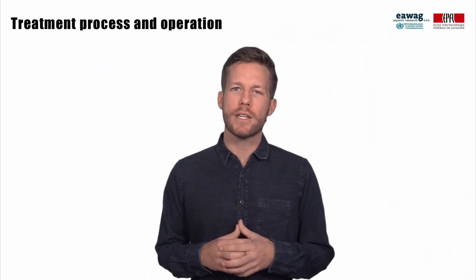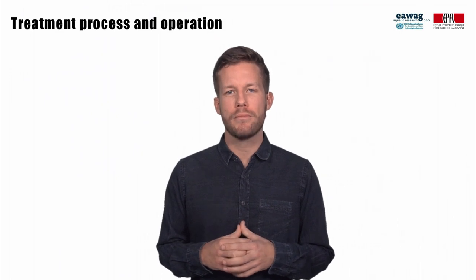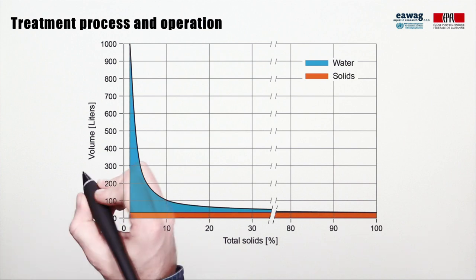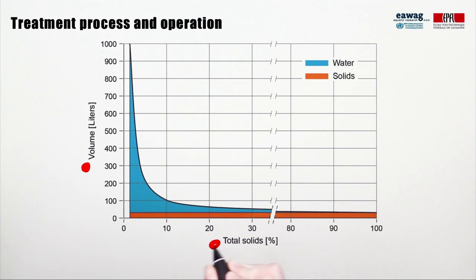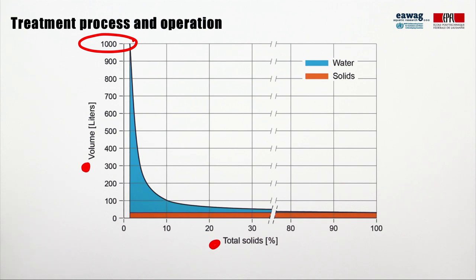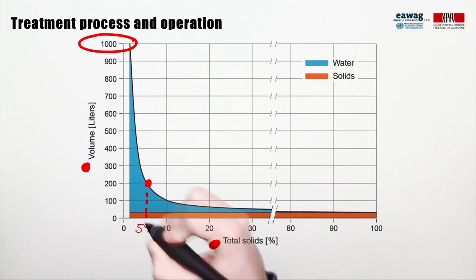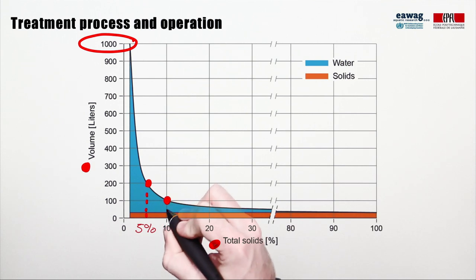So what is the benefit of a settling thickening tank? Let's consider a hypothetical example. This slide shows the change of sludge volume as a function of the solids content. As you can see from the slope of the curve, the reduction in sludge volume is highest at low solid contents. Let's assume we have 1,000 liters of sludge with a solid content of 1%, which is typical for septic tank sludge. Increasing solid content would reduce the sludge volume to 200 liters for 5% solids and 100 liters for 10% solids — a reduction of 80 and 90% of the initial volume. These are typical solids contents from settling thickening tanks in Accra and Dakar.